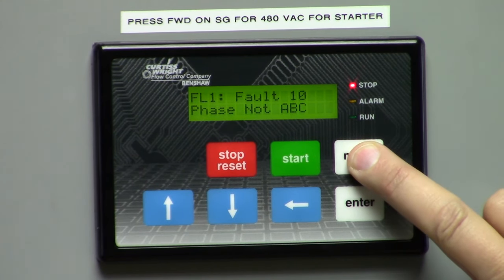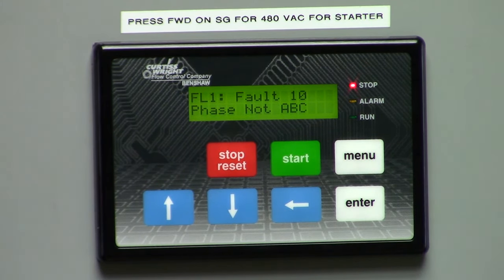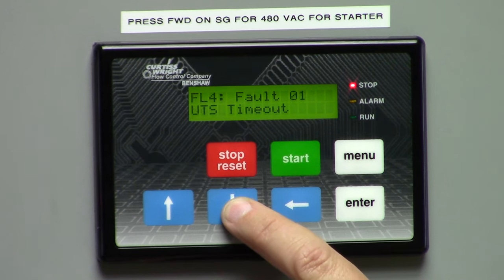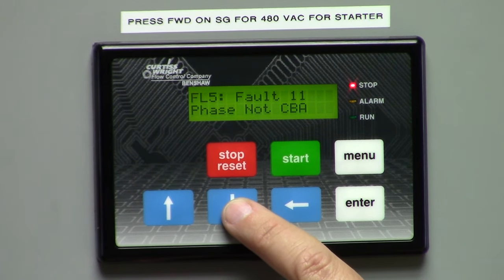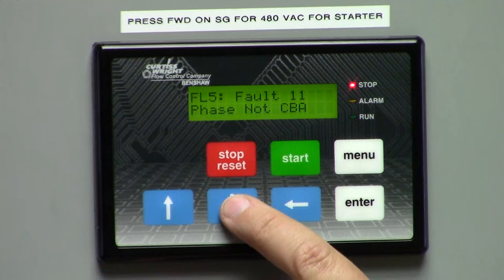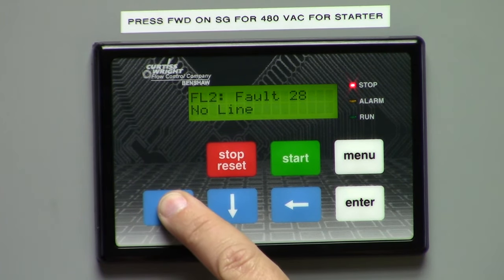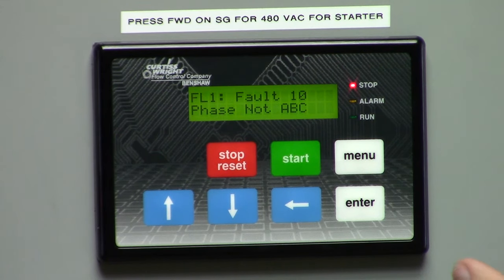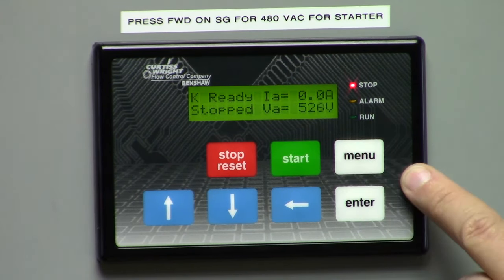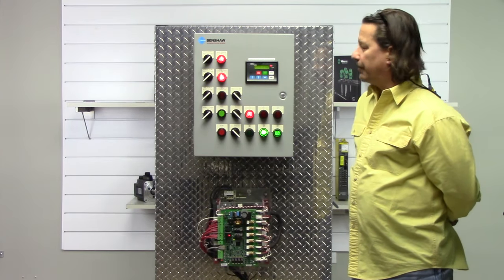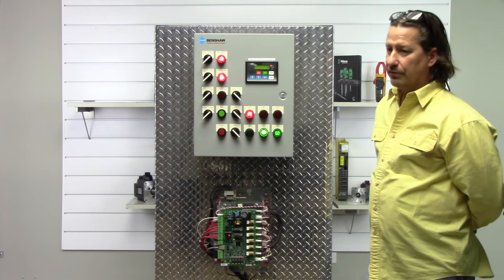There's the function group. This is not actually a parameter — this is my fault menu. This records the last five faults, so I can go down and look at my faults. This is important for troubleshooting. If we need to talk to you, we may ask you to go into the fault menu and tell us what the last fault was — that would be fault number one, which is the latest fault. Push the menu button and it brings you back to the basic default menu.